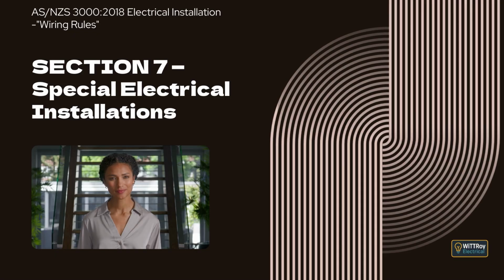Clause 7.3.8.1.1 General. This clause explains that the incoming neutral to a MEN switchboard must not be switched when connecting an alternative supply. It explains that the neutral earth connection must be made within the installation at the main switchboard, and this may require disconnection of any neutral earth link within a generation system such as an engine-driven generator. It explains that this applies to any switchboard fitted with a MEN connection, including switchboards in outbuildings regarded as main switchboards for earthing purposes.